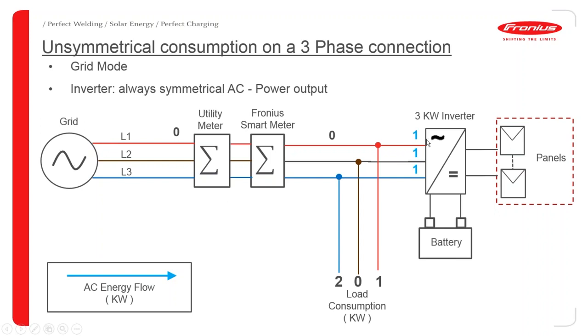So in this example, just for ease of calculation, we've got a 3 kilowatt inverter with 3 kilowatts of modules with 100% efficiency, so there's no losses in the system. And the inverter is in grid connect mode, so as you can see here, it's actually connected to the grid. So if that's producing full power, you've got 1 kilowatt per phase. In Australia, the 3-phase grid connect inverters have to have a balanced output. The utilities require it. So even if it's an unbalanced load, the inverter will always have a balanced output regardless.